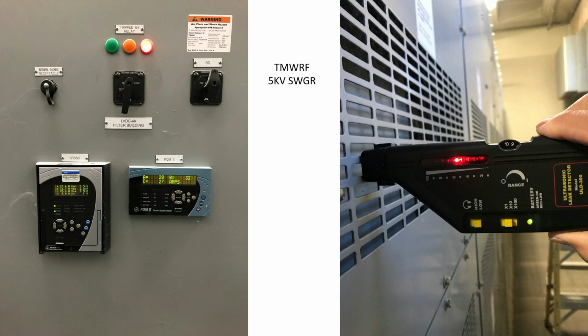And one of my jobs was also to check for issues with terminations. I thought I had this tool in my truck, but I didn't. I was going to bring it in. This guy here is an ultrasonic tester. And because this is a 4160 board, I didn't want to be opening anything up to check for looseness. But with this ultrasonic tester, as you can see, the lights start to light. It's at about the number 5 light. And I'm just measuring noise from loose terminations outside the switchboard. So this is an awesome tool for checking loose terminations.